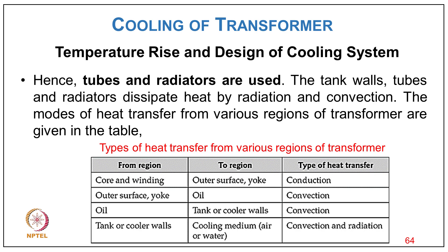Modes of heat transfer in a transformer: from core and winding to outer surface/yoke by conduction; from outer surface/yoke to oil by convection; from oil to tank/cooler walls by convection; from tank/cooler walls to cooling medium (air or water) by convection and radiation. So cooling involves conduction, convection, and radiation.